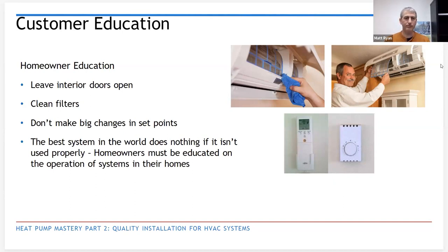Matt, in terms of things the homeowners can do for maintenance, we've talked about cleaning the filters on the inside. Is there anything they should pay attention to on the outdoor unit? Outdoor would just be watching the coil on the outdoor unit. That's usually something that would be maintained by an HVAC contractor. Some homeowners feel savvy enough to do it. Depending on location, if you've got a lot of cottonwood around your area, that'll build up on the outdoor units really fast. Some homeowners are capable of dealing with that. Others will have maintenance agreements and we'll take care of that, but not a whole lot. With the mini splits, it's really making sure coils are clean.